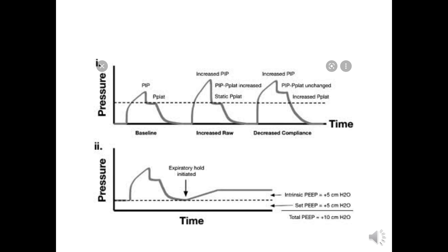The third condition shows decreased compliance: both the peak inspiratory pressure and the plateau pressure increase, but the difference between them remains unchanged. The lower graph shows the end expiratory hold procedure from which we can measure the intrinsic PEEP or auto-PEEP.